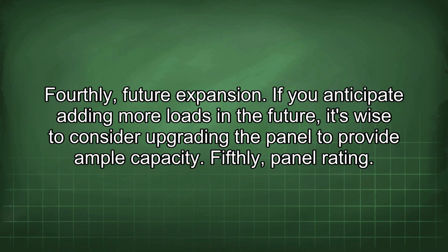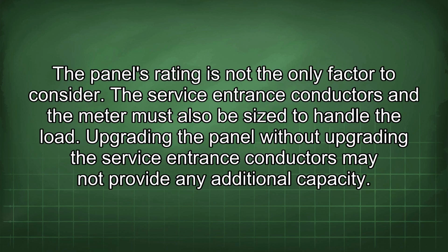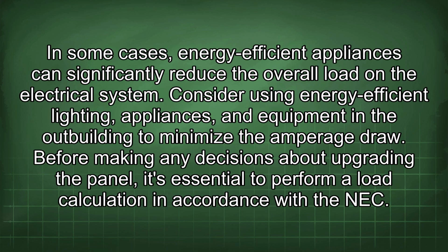Fourthly, future expansion. If you anticipate adding more loads in the future, it's wise to consider upgrading the panel to provide ample capacity. Fifthly, panel rating. The panel's rating is not the only factor to consider. The service entrance conductors and the meter must also be sized to handle the load. Upgrading the panel without upgrading the service entrance conductors may not provide any additional capacity. In some cases, energy-efficient appliances can significantly reduce the overall load on the electrical system.